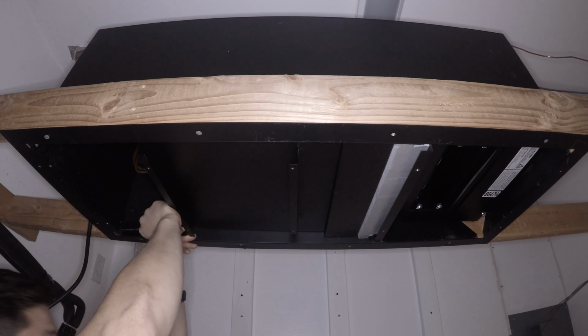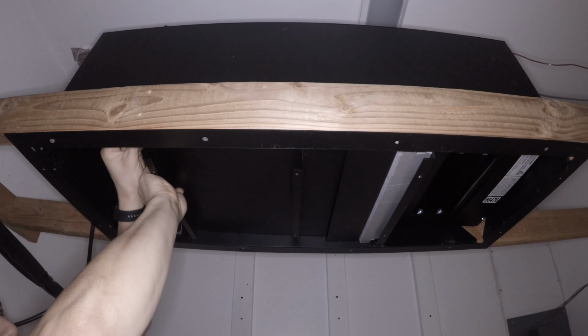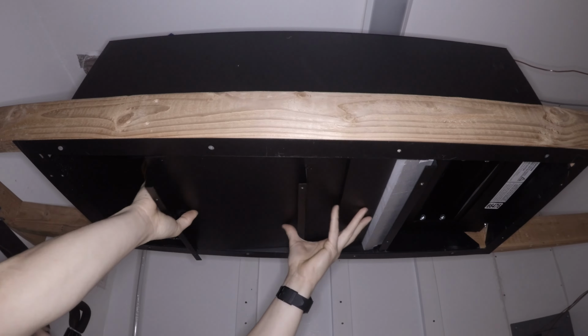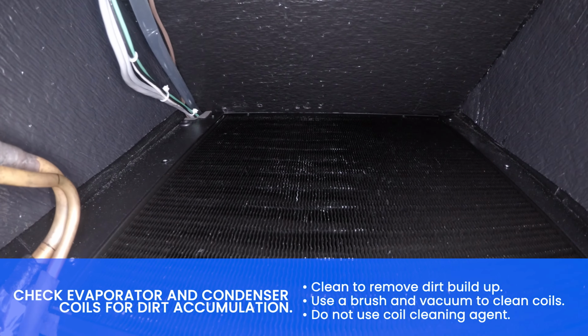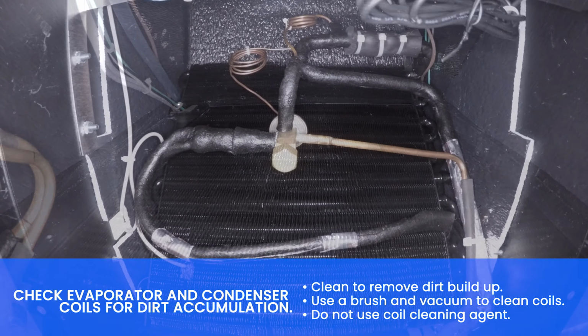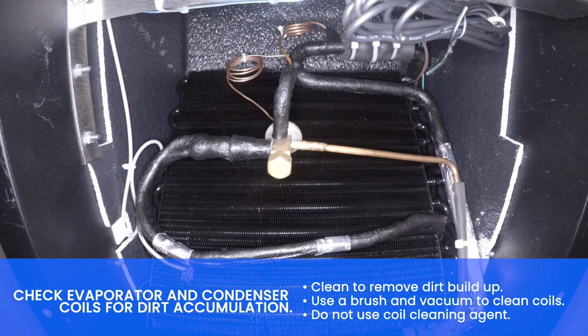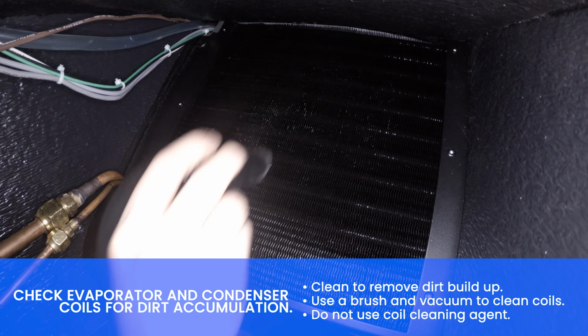Remove the 2 thumb screws securing the drip tray in place and drop the drip tray. Check coil for dirt accumulation. Clean to remove dirt buildup. Use a brush and vacuum to clean the coil.